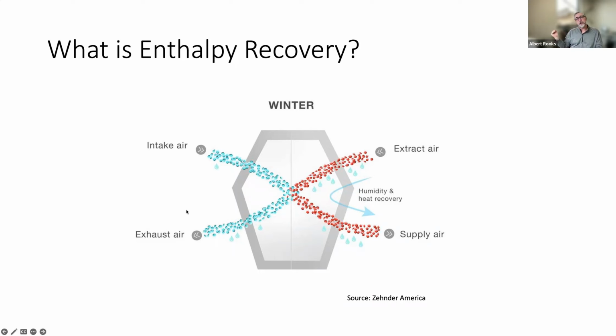And as we flow air through our building, we're going to push any moisture inside the building out. So in a condition where we're up in the Sierras and it's cold outside and the humidity is relatively low, we're going to constantly be losing humidity unless we have a building full of a lot of people that are breathing, and maybe they got a couple of wet dogs or some way of building moisture inside the building. So enthalpy recovery is a way to control that.